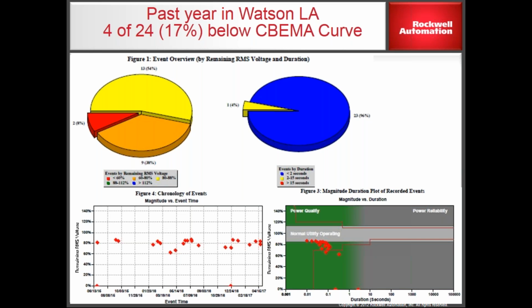That's the spec. Even though a data sheet typically says voltage plus or minus 10%, that's accurate out here. But if you have an event that lasts a tenth of a second, the components inside are designed to deal with a drop to about 70%, or up as high as 120% - almost plus or minus 25% on those short-term events.